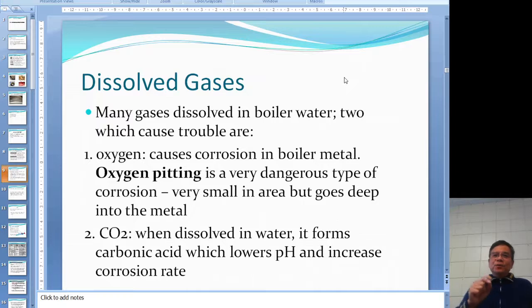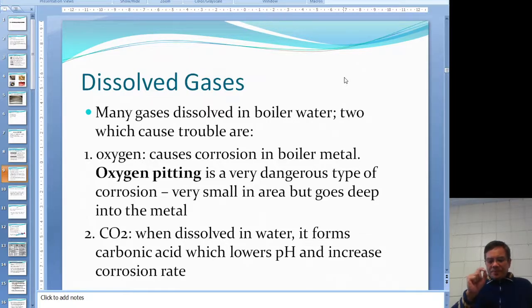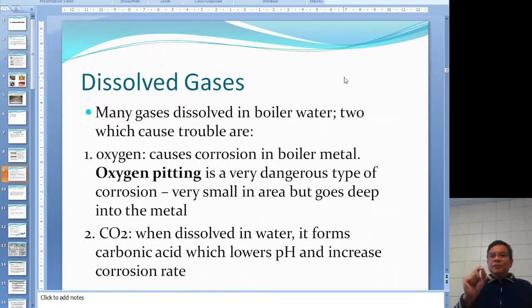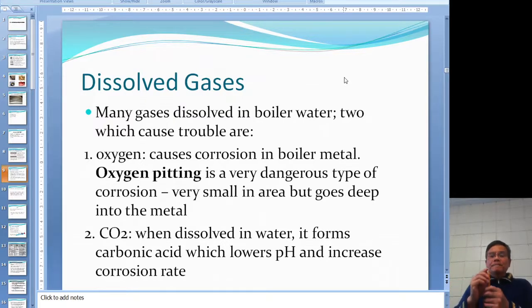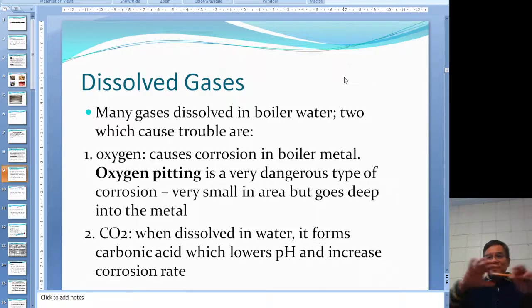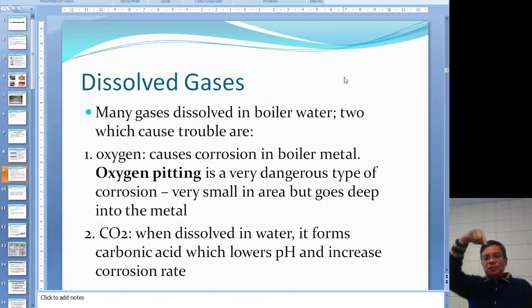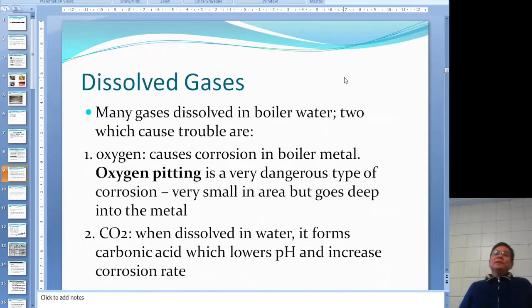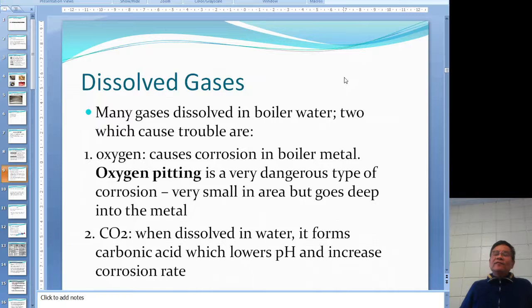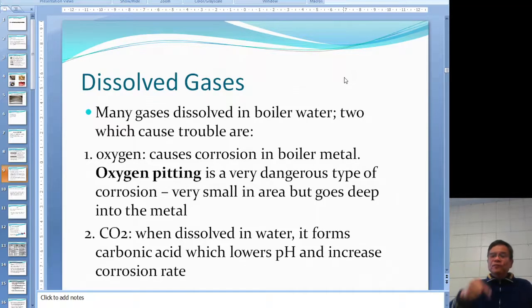A common term in operating engineering is oxygen pitting. This type of corrosion is particularly bad because it's very small in diameter — maybe a couple of millimeters — but instead of spreading wide, it goes deep. The tip of a pencil head in size, but it grows deeper. Since a boiler tube may only be 5-6 mm thick, this pitting can easily go through the tube wall.